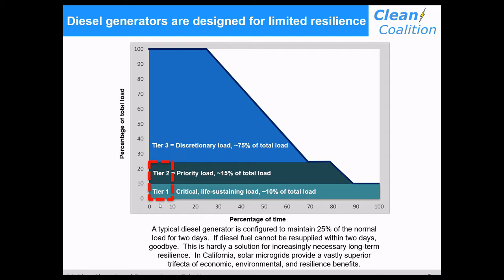It's typically designed to keep the tier 1 and tier 2 loads on, and that's about 25% of the total load. But an average diesel generator installation only keeps those loads on for 2 days, so a very small percentage of the time. When the Clean Coalition talks about indefinite resilience, we're talking about forever, and as a proxy for indefinite, we use 30 days. This red rectangle represents the amount of resilience you'll get from a typical diesel generator installation - it's very limited in terms of how long it can keep the loads on and how much load it will keep on. So it's 25% of the typical load for about 2 days, and after that, it's lights out. It's goodbye. That's an important concept to keep in mind.